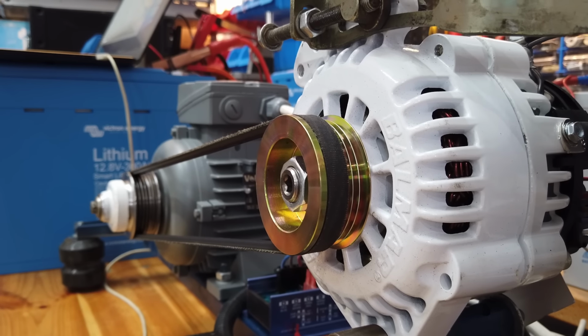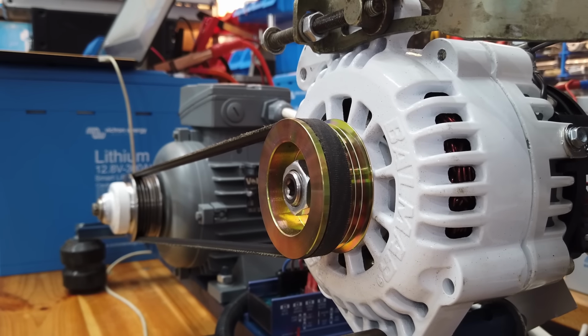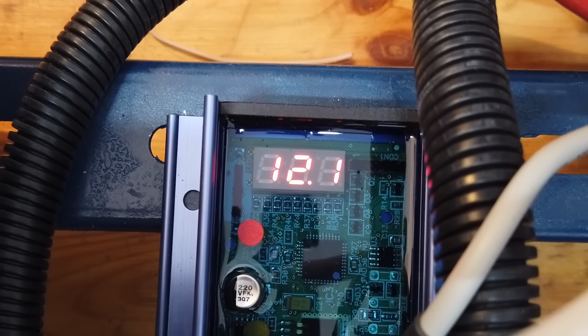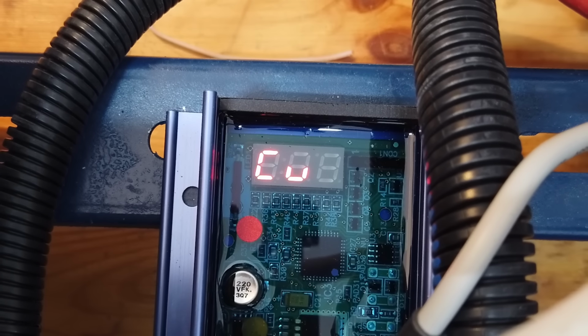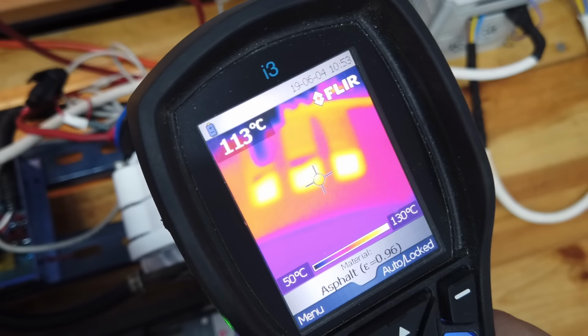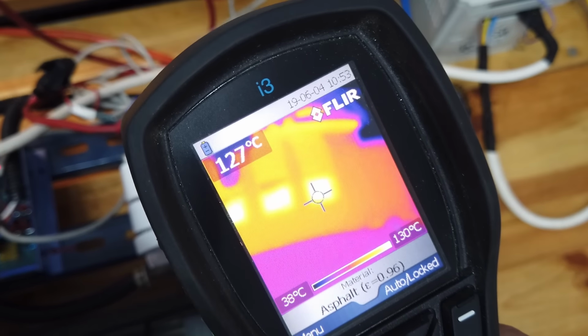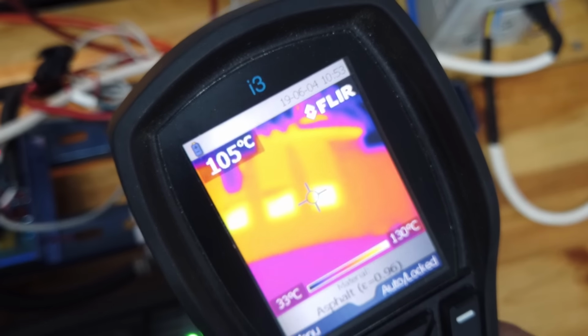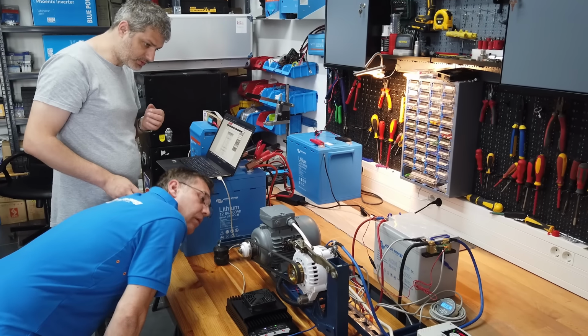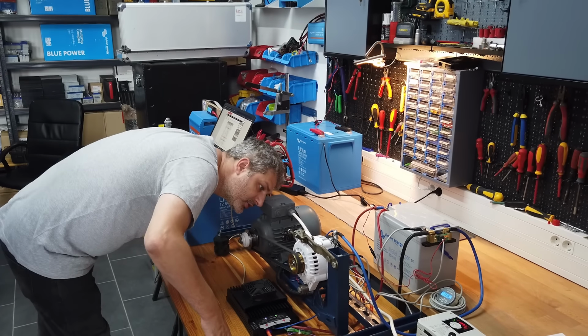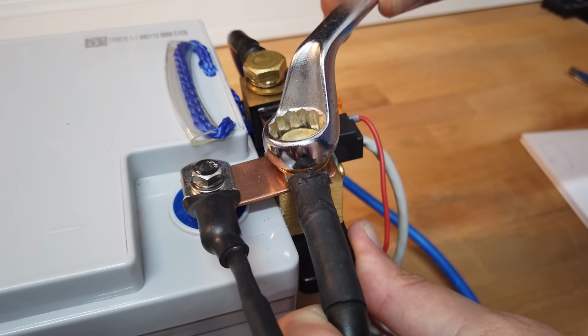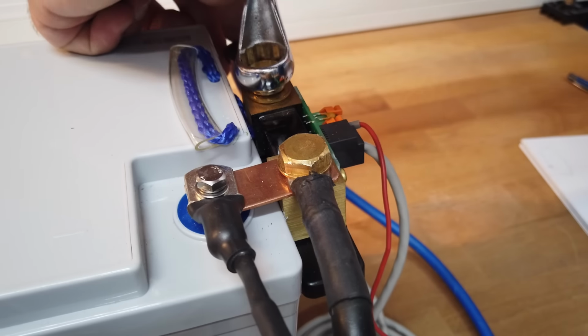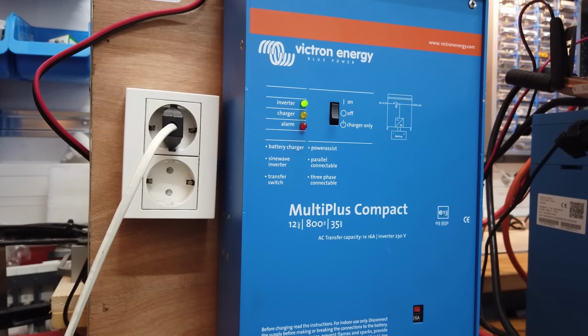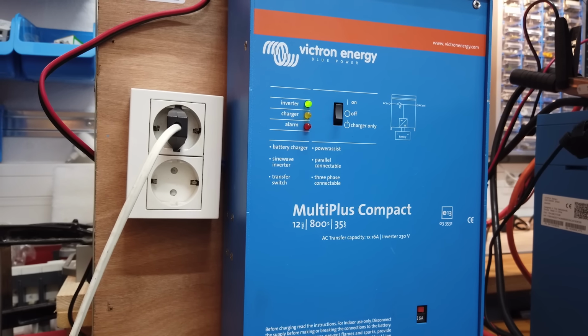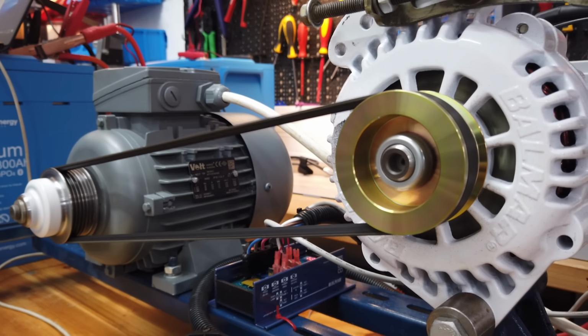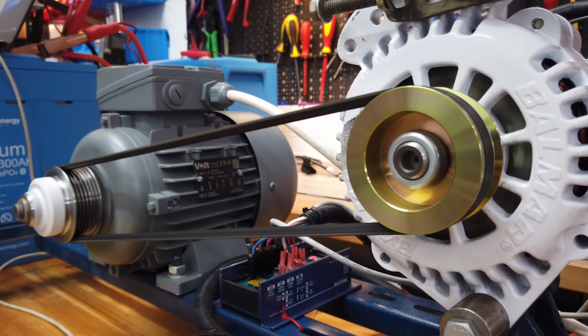Another solution is to fit an alternator and regulator with a temperature sensor like the Balmar that we've shown in this video. When the alternator gets too hot, the regulator dials it down to keep it within the allowed temperature range. Lastly, you can limit the current by installing a current limiter or DC to DC charger. The other issue, not demonstrated in this video, is that many lithium systems disconnect the battery from the charging source once fully charged. This can damage the alternator regulator if not done properly.